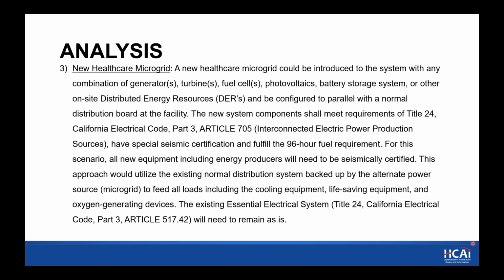A new healthcare microgrid could be introduced into the system with any combination of generators, turbines, fuel cells, PVs, battery storage, or other on-site distributed energy resources, and be configured to parallel with the normal distribution board at the facility. The new system components would need to meet Title 24, Article 705, interconnected electric power production, have special seismic certification, and fulfill the 96-hour fuel requirement. For this scenario, all new equipment, including energy producers, would need to have special seismic certification.